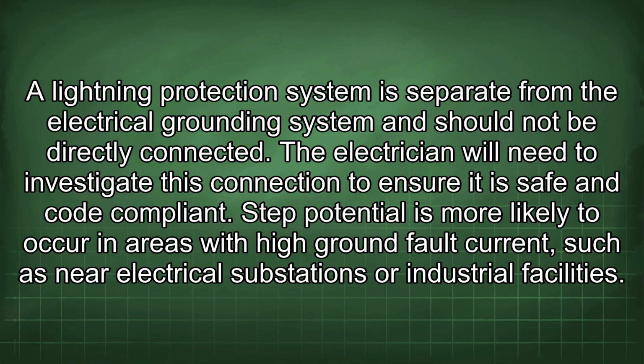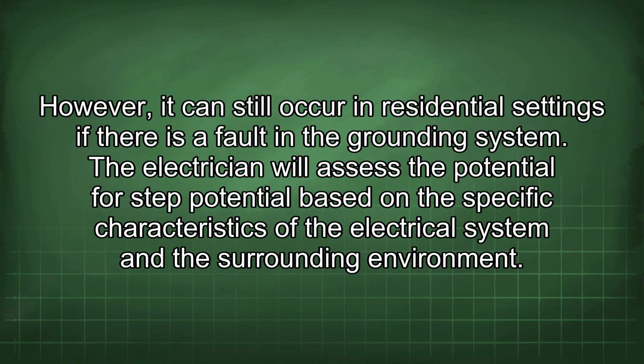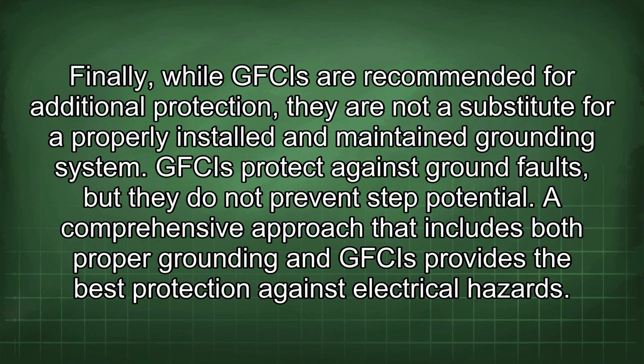Step potential is more likely to occur in areas with high ground fault current, such as near electrical substations or industrial facilities. However, it can still occur in residential settings if there is a fault in the grounding system. The electrician will assess the potential for step potential based on the specific characteristics of the electrical system and the surrounding environment. Finally, while GFCIs are recommended for additional protection, they are not a substitute for a properly installed and maintained grounding system. GFCIs protect against ground faults, but they do not prevent step potential. A comprehensive approach that includes both proper grounding and GFCIs provides the best protection against electrical hazards.